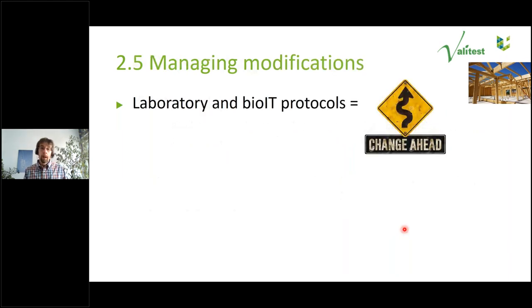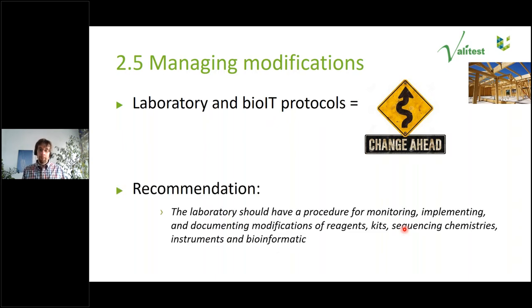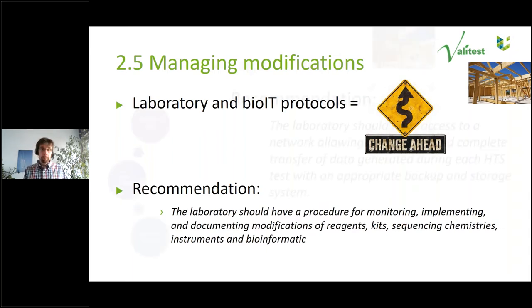Managing modifications is quite important. An ELISA test may remain unchanged for years or decades, but with HTS you have regular upgrades: machine upgrades, library preparation kit upgrades, and most frequently upgrades of bioinformatic protocols — new software offering greater speed, accuracy, or specificity. From the beginning you must think about how to monitor, implement, and document modifications applied in the laboratory: reagents, kit versioning, the sequencing machine, and the bioinformatics.